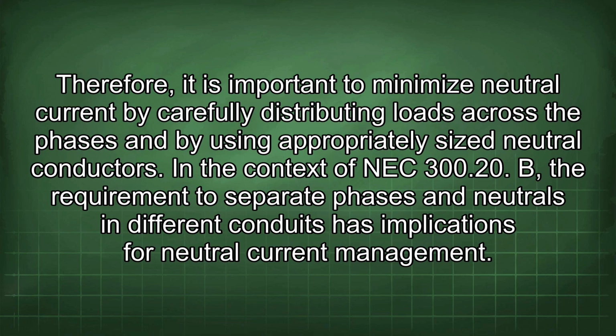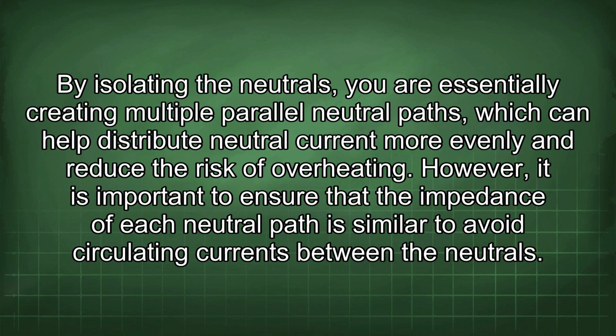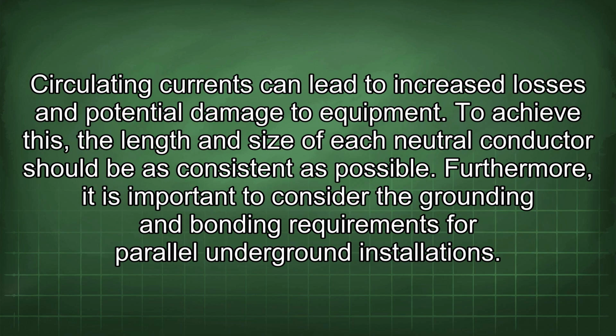Therefore, it is important to minimize neutral current by carefully distributing loads across the phases and by using appropriately sized neutral conductors. In the context of NEC 300.20(B), the requirement to separate phases and neutrals in different conduits has implications for neutral current management. By isolating the neutrals, you are essentially creating multiple parallel neutral paths, which can help distribute neutral current more evenly and reduce the risk of overheating. However, it is important to ensure that the impedance of each neutral path is similar to avoid circulating currents between the neutrals. Circulating currents can lead to increased losses and potential damage to equipment. To achieve this, the length and size of each neutral conductor should be as consistent as possible.